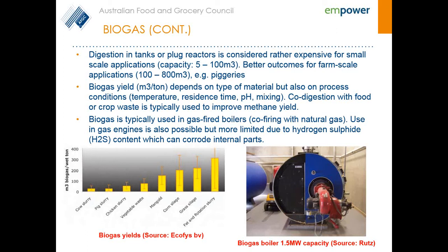As mentioned earlier, we have the sulfur content in the form of hydrogen sulfide, which can create corrosion problems and also needs to be taken into account. What we've seen in some industries is that when the sulfur content is high, it will make sense to co-fire biogas at low ratios in combination with natural gas. Below are a few diagrams and photos showing different biogas yields that can be achieved using different types of materials.